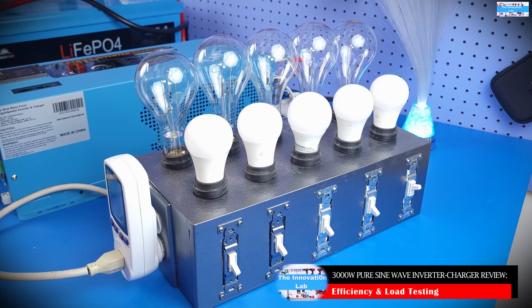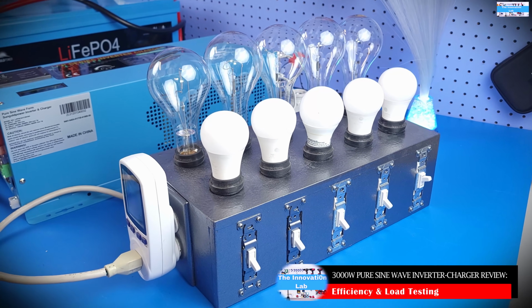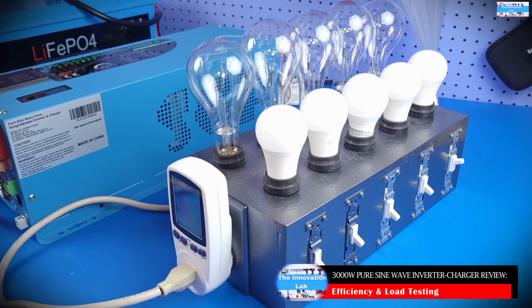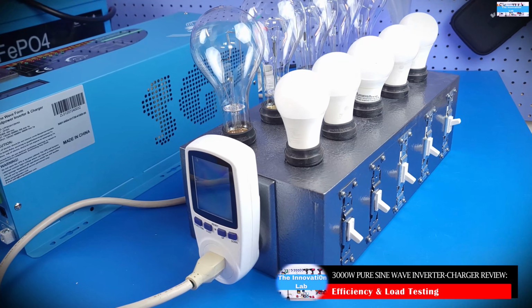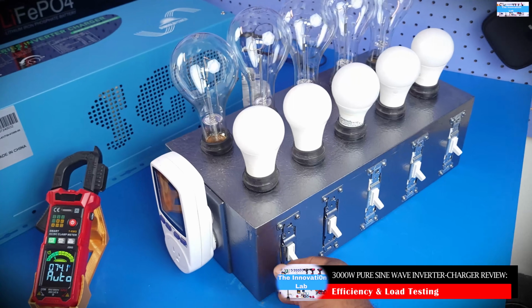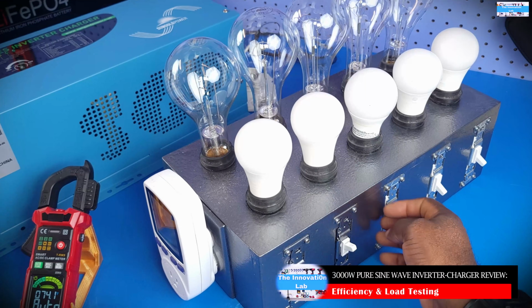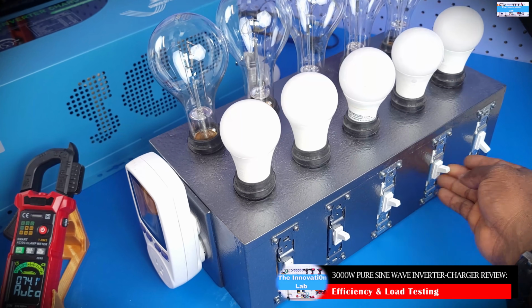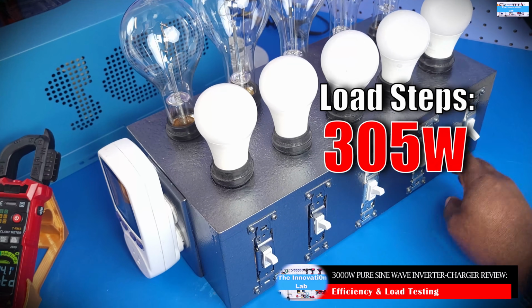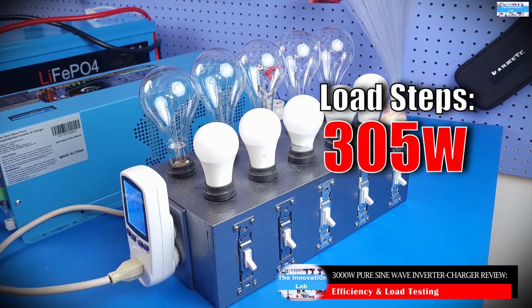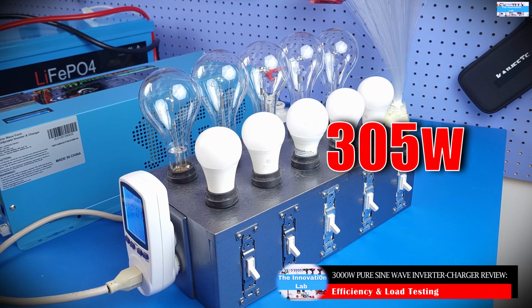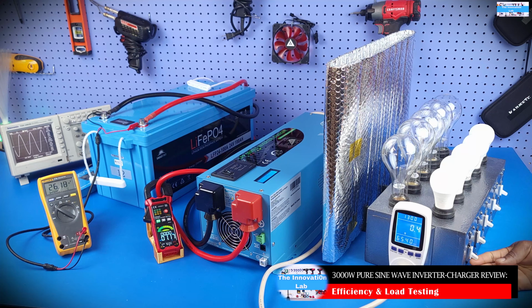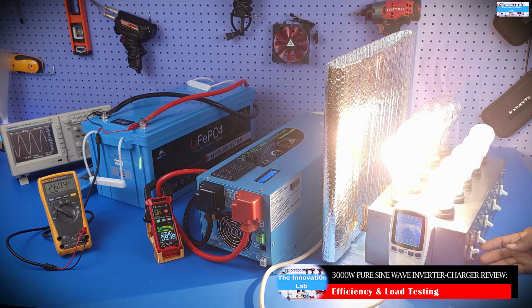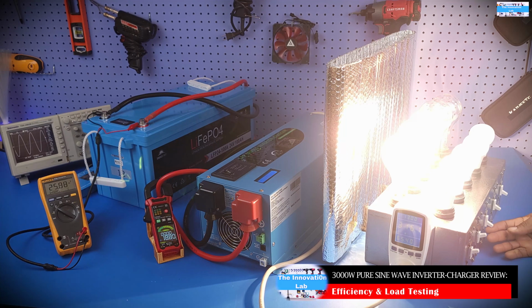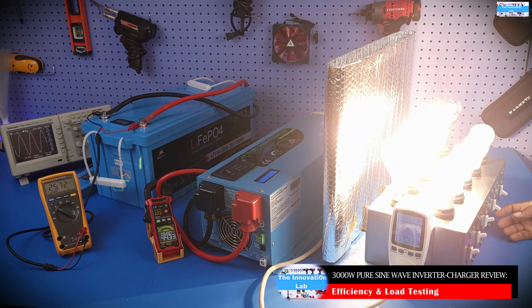For the initial load test and efficiency measurements, we're using our DIY 5-channel AC load box, which allows us to do a 300 watt load step. We installed a 300 watt load on each channel and connected the load box to the power inverter. With all the test loads installed, we incrementally stepped the load 300 watts at a time until we got to a total load of about 1600 watts.